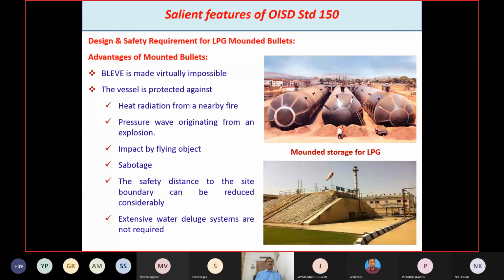Here, one important point is to be noted. The liquid in contact with the metallic surface of the vessel is safe, because it absorbs the heat for changing from liquid to vapor. Whereas the metallic surface in contact with the vapor space is very vulnerable, as there is no heat conduction. Due to continuous heat and frequent opening and closing of the safety relief valve, the liquid level inside the vessel will start reducing, exposing more area of vapor space. The vapor space will be continuously heated and will deteriorate. At one point of time, the weakest point will rupture and open.